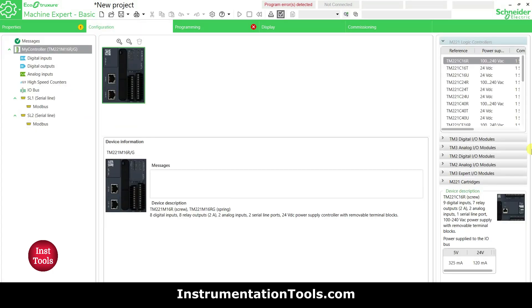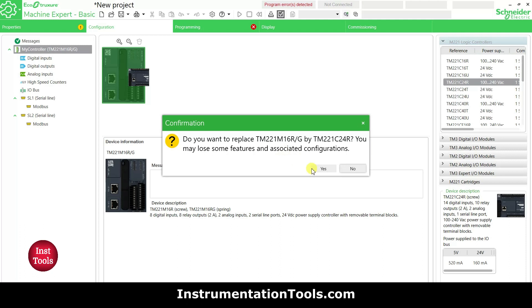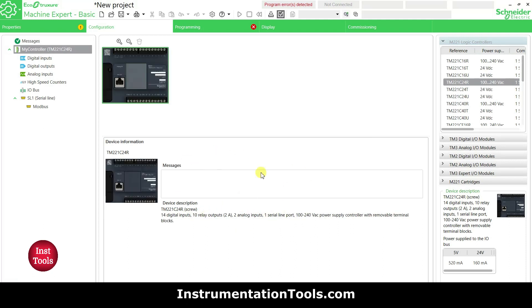I will go to the Configuration tab where there is a list of different logic controllers. I will select TM221C24R. This logic controller has 14 digital inputs, 10 relay outputs, 2 analog inputs, 1 serial line port, and a 100 to 240 volt AC power supply with removable terminal blocks.